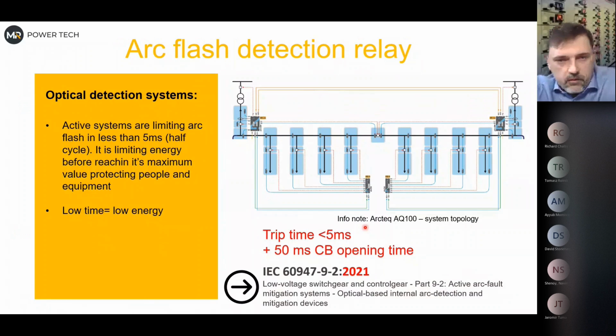The next thing that we can do, and for this project, was an arc flash detection relay. At least I was recommending this. The arc flash detection relay has sensors that detect the arc flash, detecting the light, or the pressure, depending on what kind of system you have. It also has a voltage and current system to detect what's happening. Then it sends the signal to the low voltage breakers, depending on your network configuration, and also to the medium voltage breaker, because we would like to protect this line side and the transformer.